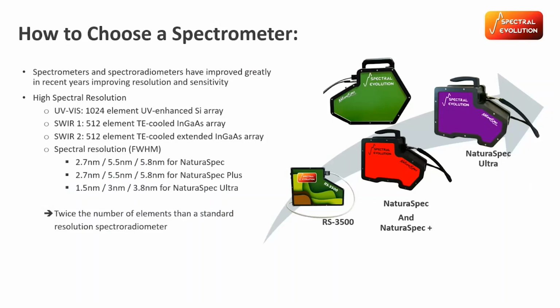We have a host of different spectrometers that are primarily separated by their resolution. This is our NaturaSpec series. These are spectroradiometers, so they can do energy measurements. We have a standard resolution instrument, which is the RS-3500. That was industry standard for many years, but in recent years, we've made great improvements on our instruments, and we've announced the NaturaSpec and the NaturaSpec Plus. This improves our spectral resolution without sacrificing signal-to-noise ratio.